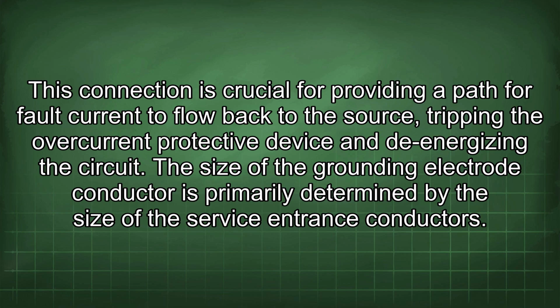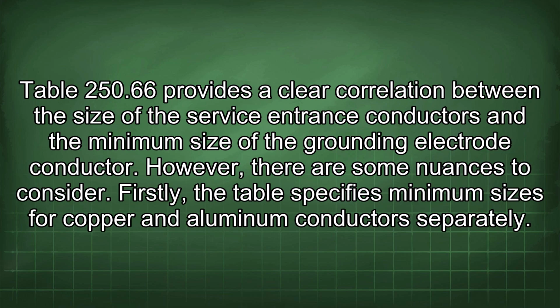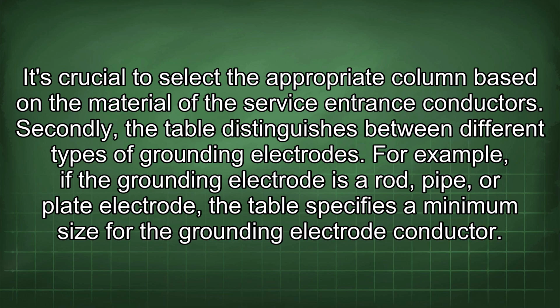The size of the grounding electrode conductor is primarily determined by the size of the service entrance conductors. Table 250.66 provides a clear correlation between the size of the service entrance conductors and the minimum size of the grounding electrode conductor. However, there are some nuances to consider. Firstly, the table specifies minimum sizes for copper and aluminum conductors separately. It's crucial to select the appropriate column based on the material of the service entrance conductors.